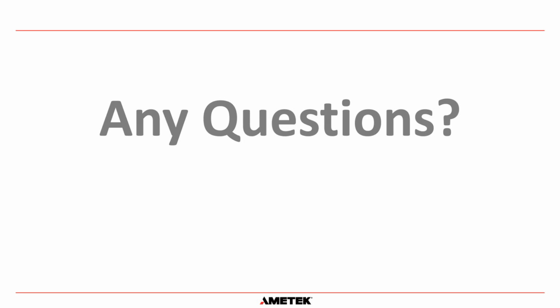I did see a question in the chat bar as well. Can you feed one UPS to another UPS on the maintenance bypass terminal? Yes, that is called a Cascade UPS. Okay, that's for Meshach. That is what I mentioned, Cascade. You feed one UPS, that would be UPS B, would feed into the static switch bypass terminal on the UPS A. Okay.